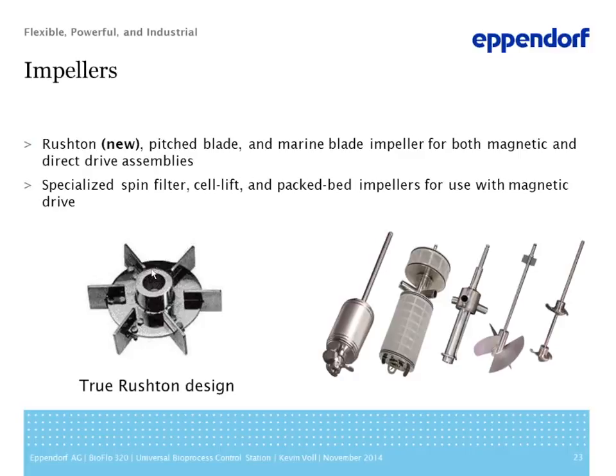Impellers. We've always offered a very large portfolio of standard and Eppendorf exclusive impellers. We've now also integrated a true Rushton design into the 320 vessels, depicted in the bottom left-hand corner. We're still able to achieve some of the same high KLAs and OTRs that we've always achieved in fermentation. Our vessels have been shown to achieve more than 350 millimoles per liter per hour, which is extremely high, and one of the highest in the market today, with no change here. We were just able to incorporate a true Rushton design, basically a fin bisecting the disc. On the right-hand side, you see a depiction of some of our proprietary impellers: the cell lift impeller for bubble-free aeration, and the draft tube impeller, used for our packed bed reactor incorporating our fiber cell discs.